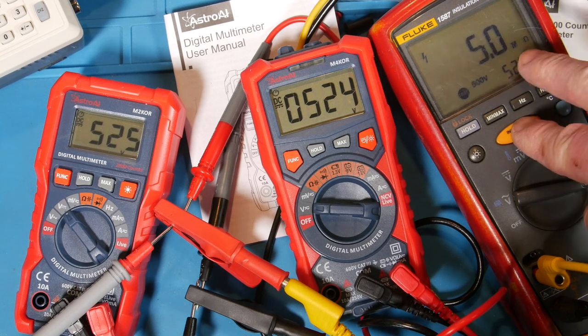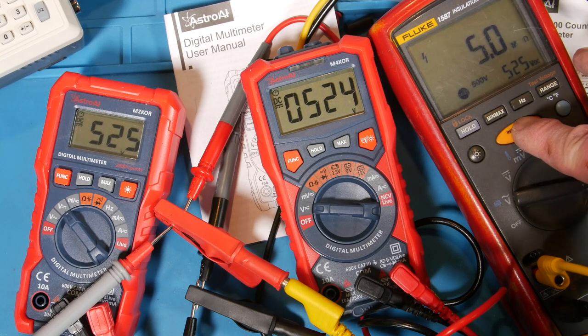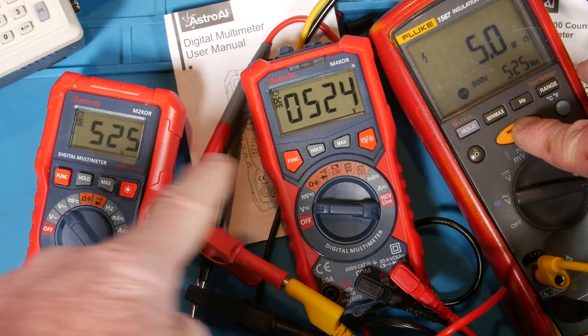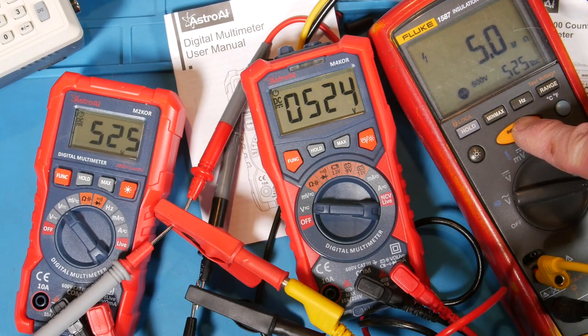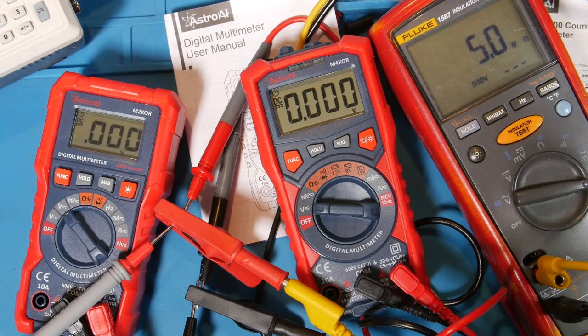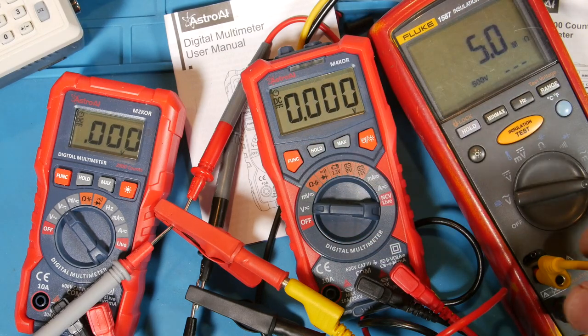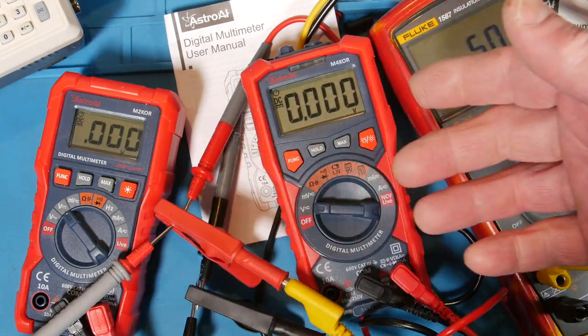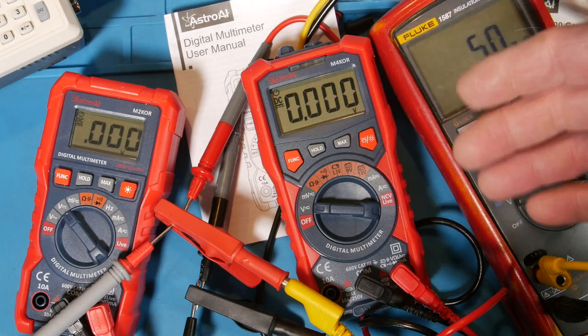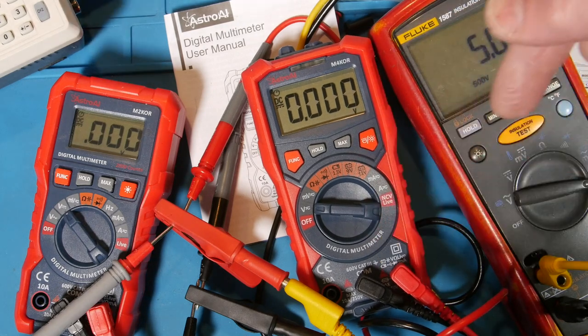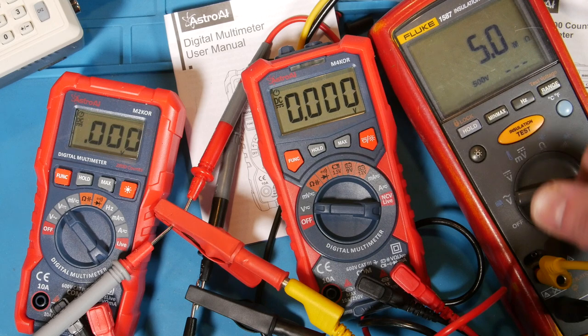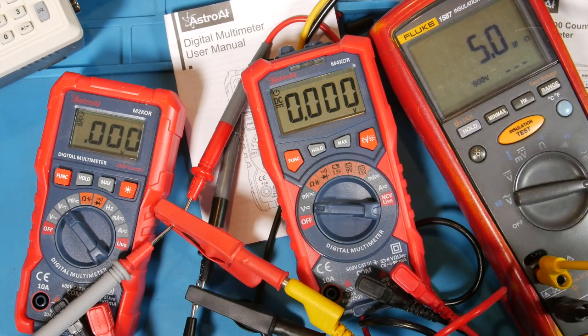Right here on my meter, the Fluke, it says 525, and yeah, we're pretty much green. So it passes the high voltage test. At 1,000 volts, they're going to beep at you for anything over 600. But it's only rated for 600 and I hit it with 1,000. So if that makes you feel better about the safety, I hope it does.